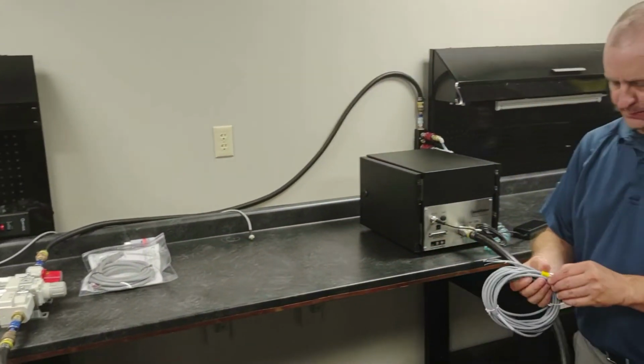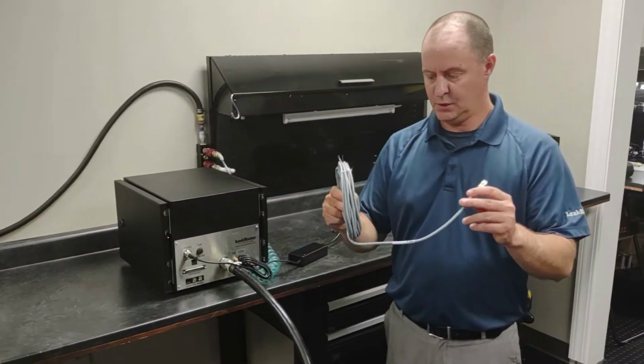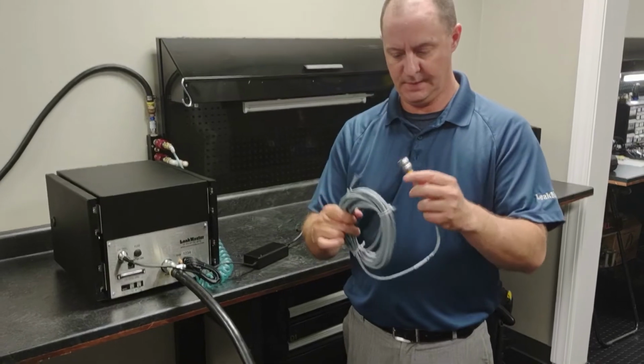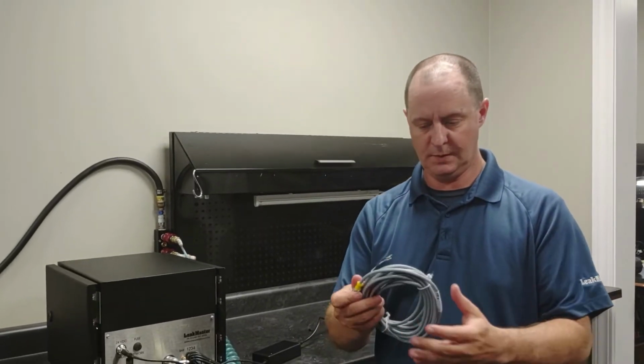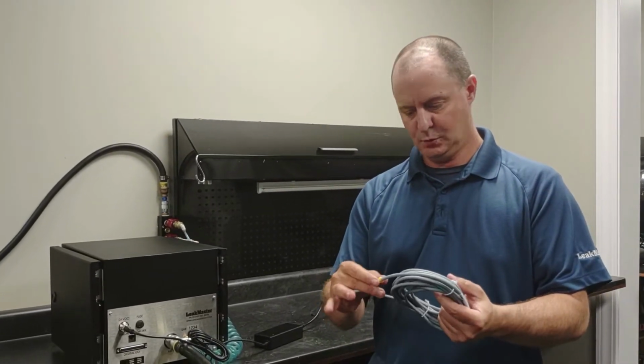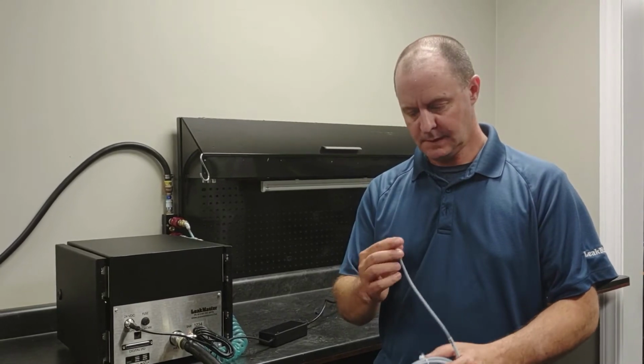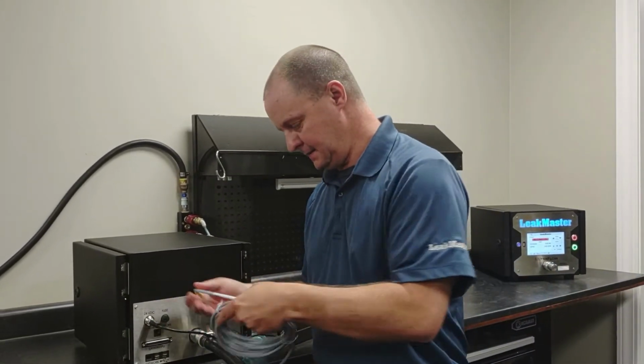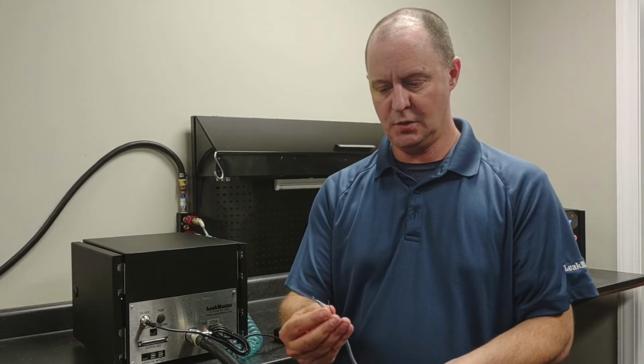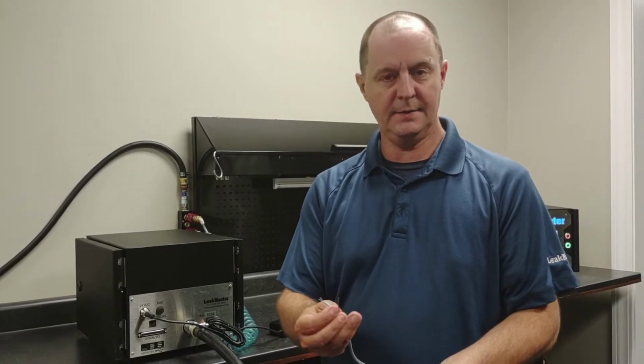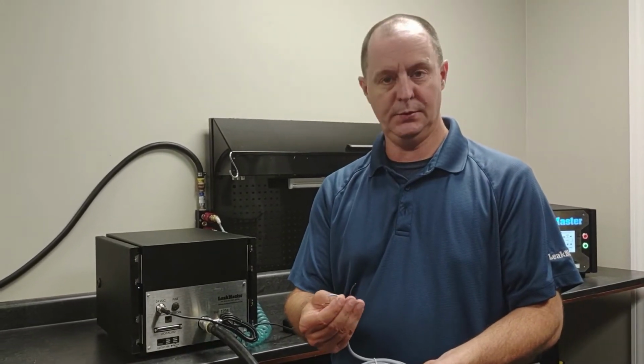Now, if you do have a 24 volt power supply on your machine, then you would not have purchased this, and you would have been delivered an M12 Turck connector. So you would just plug this guy into here. The other end is going to go back in your control panel, and you're going to tie the brown to 24 volts, and you're going to tie the blue to your common.